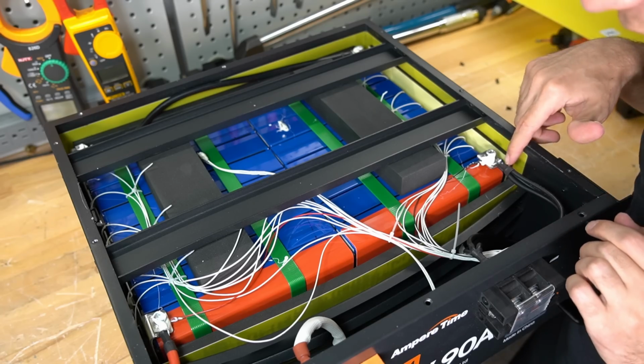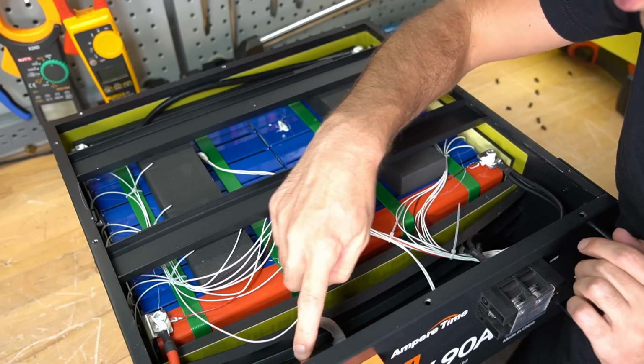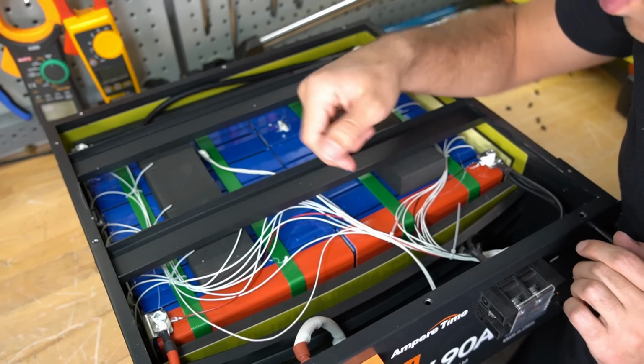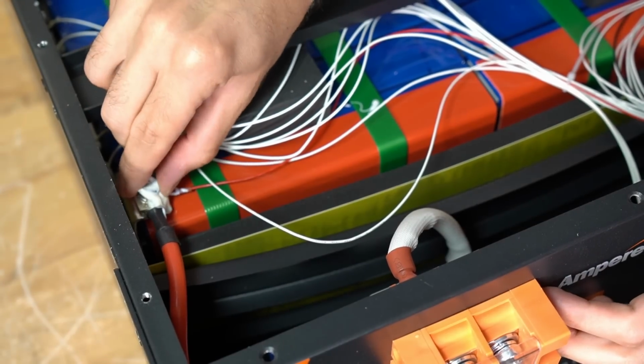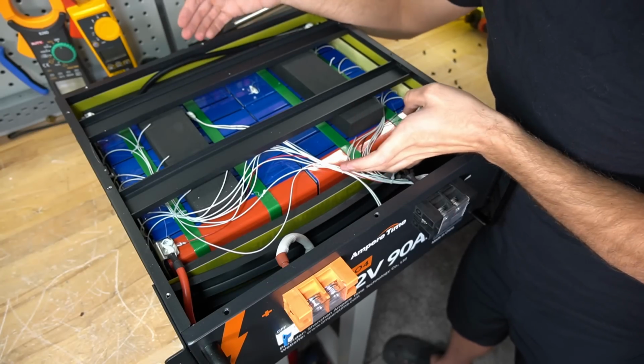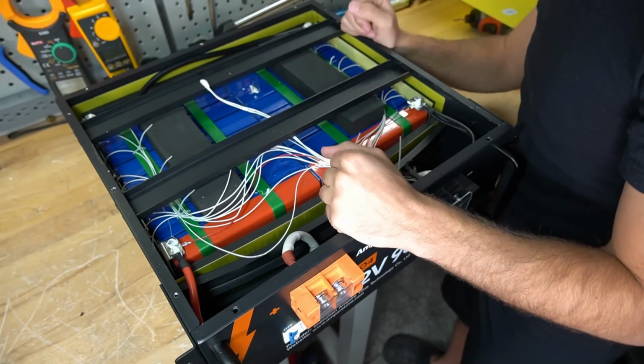The main connections are nice. These are hydraulically crimped and it's protected from the circuit breaker. But this terminal is like bent and these packs aren't even lined up. There is no low temp sensor.